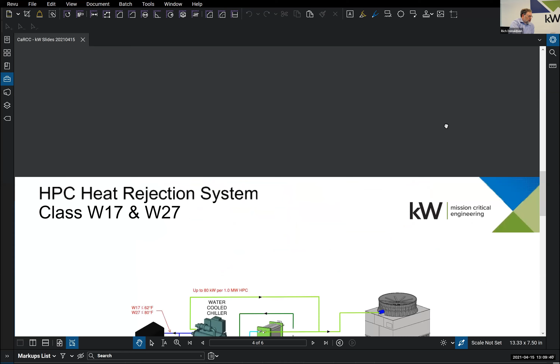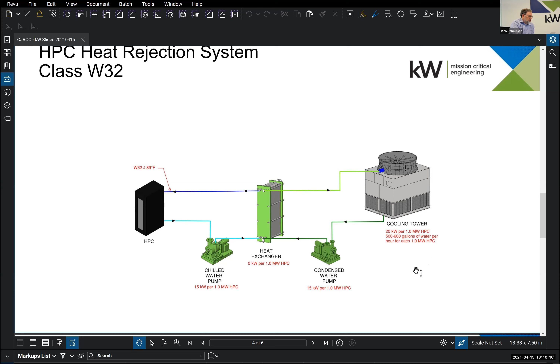If we now look at the W32 system, now we're looking at 89-degree water. We've simplified it a good bit. We still have some sort of heat rejection cooling tower outside, still at 20 kW per 1 megawatt. We still have a heat exchanger, but now with this higher temperature, this cooling tower can make the right temperature, and we don't need the chillers. We still have a couple of pumps, but now we've reduced that cooling down to 50 kW per 1,000 kW, or 1 megawatt, of HPC load.